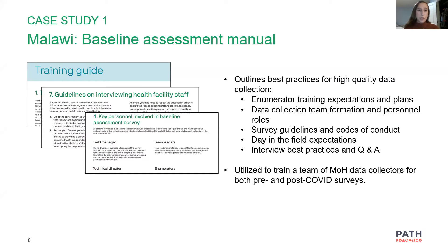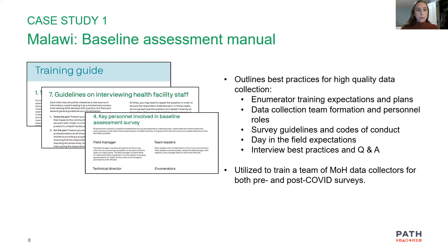In Malawi, this guidance was rapidly implemented to train a team of Ministry of Health data collectors, both for the baseline assessment prior to the pandemic and during COVID-19. The baseline assessment covered 21 district and regional referral hospitals, and the expanded biomedical equipment survey during COVID-19 covered 76 facilities. The two collected slightly different data — the COVID-era survey had more data points related to oxygen and respiratory care, while the baseline was critical for collecting data on critical care capacity. The biomedical equipment survey was also used to estimate total oxygen production capacity and estimate demand across the health system.